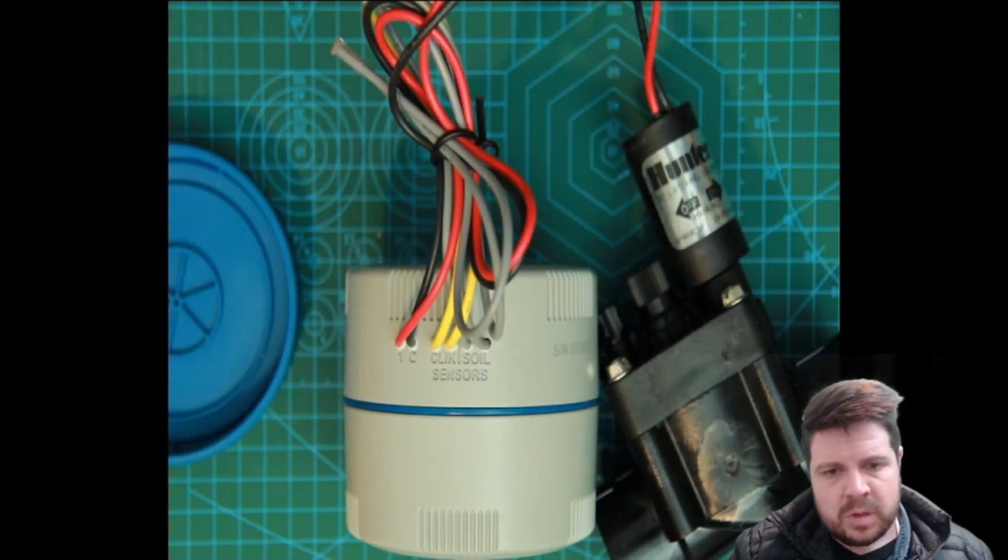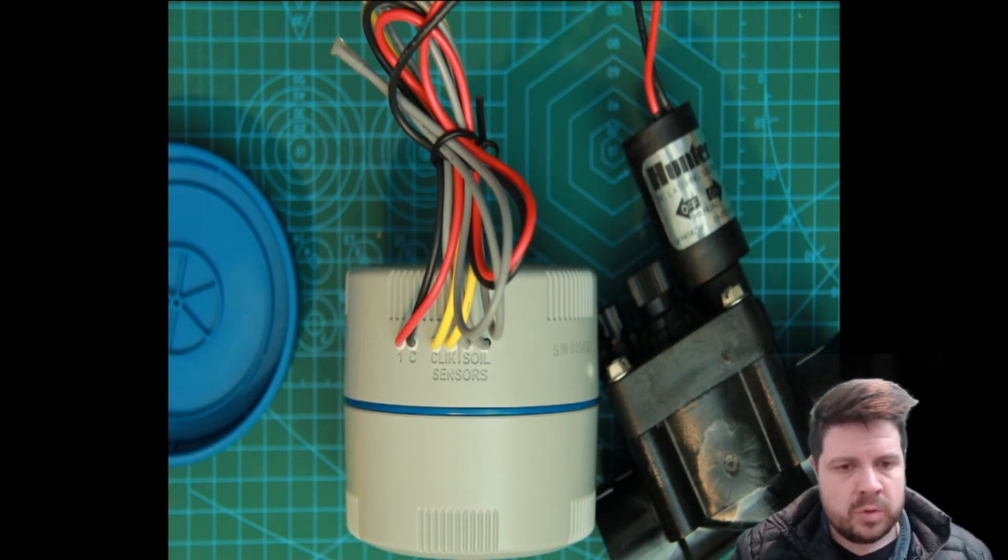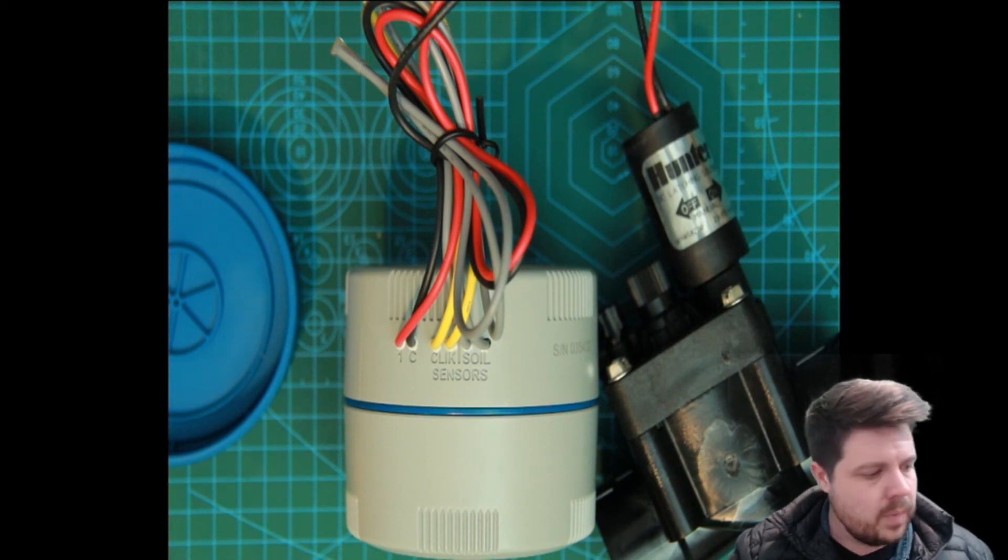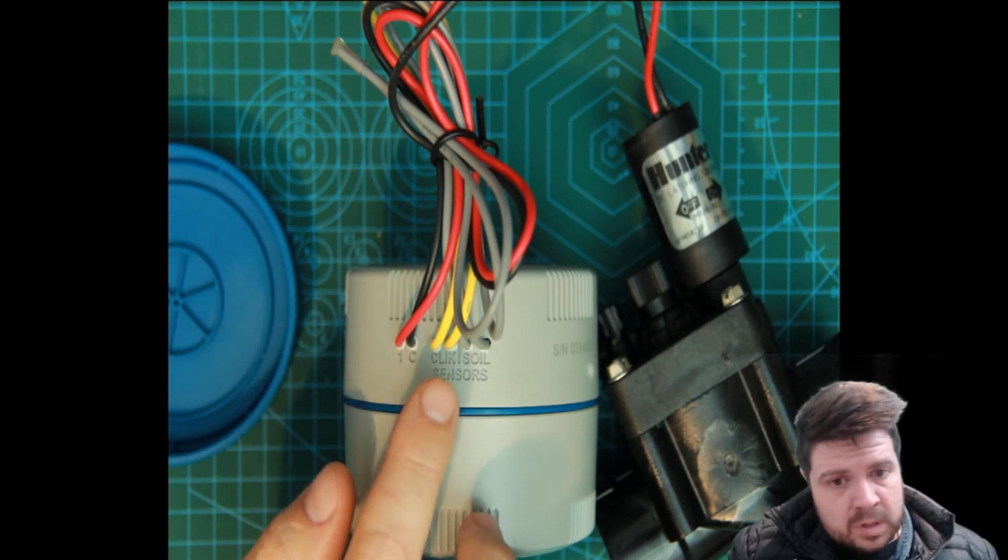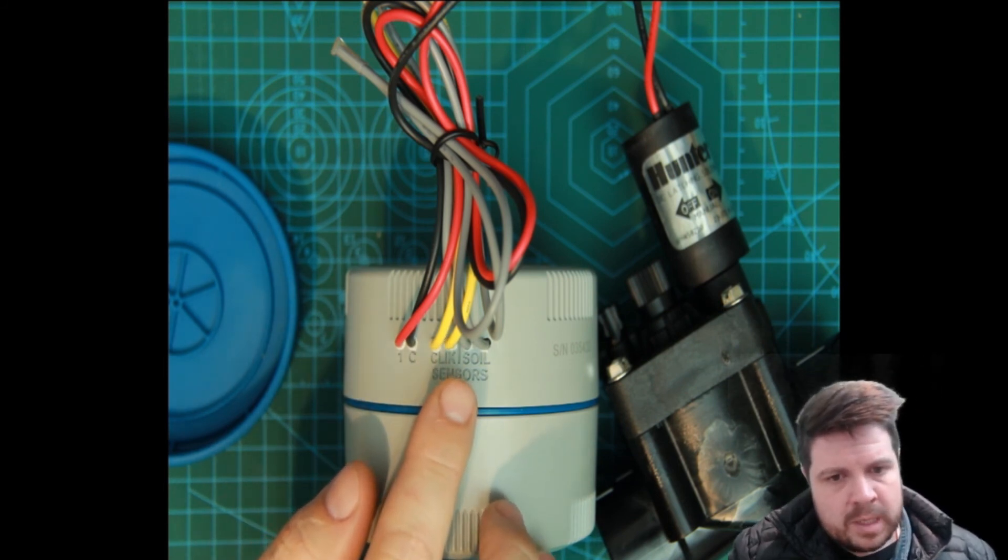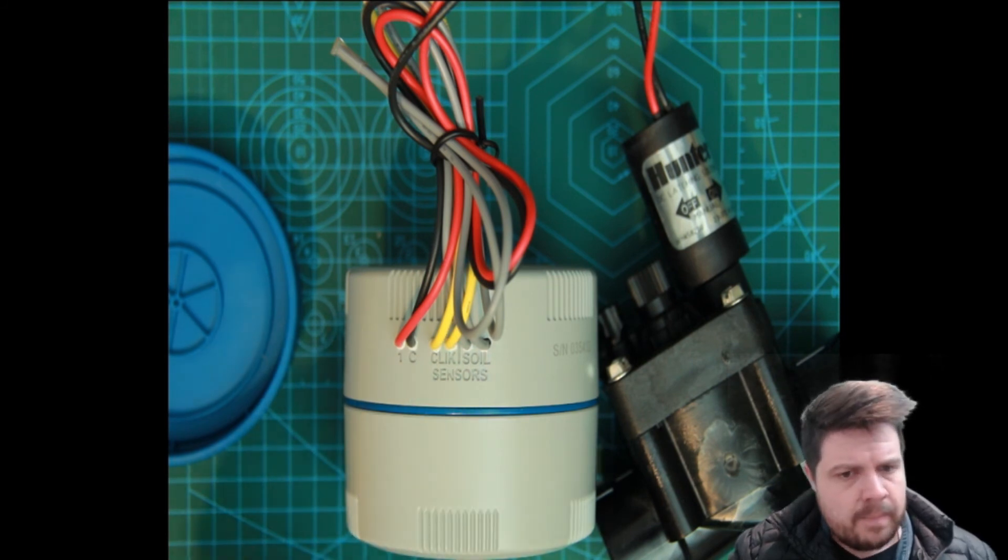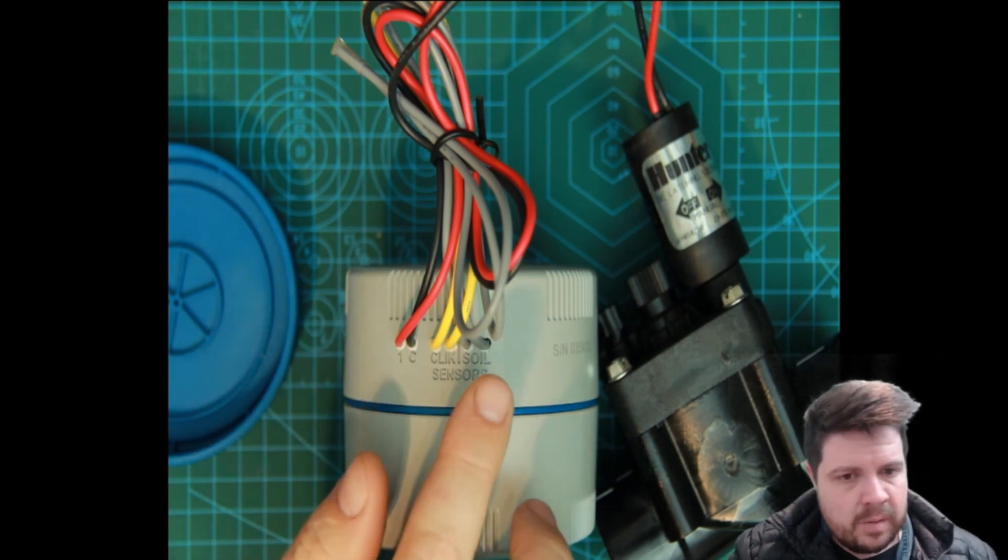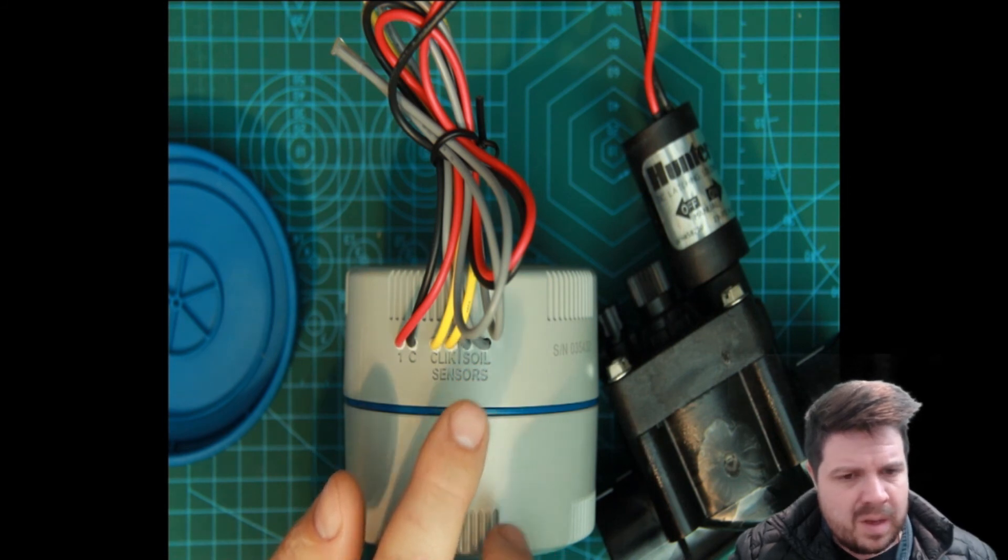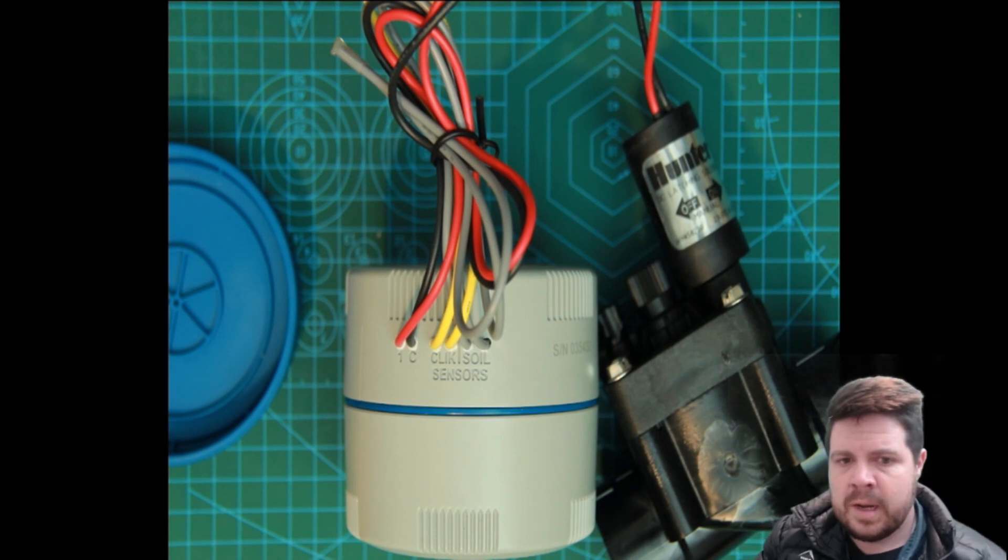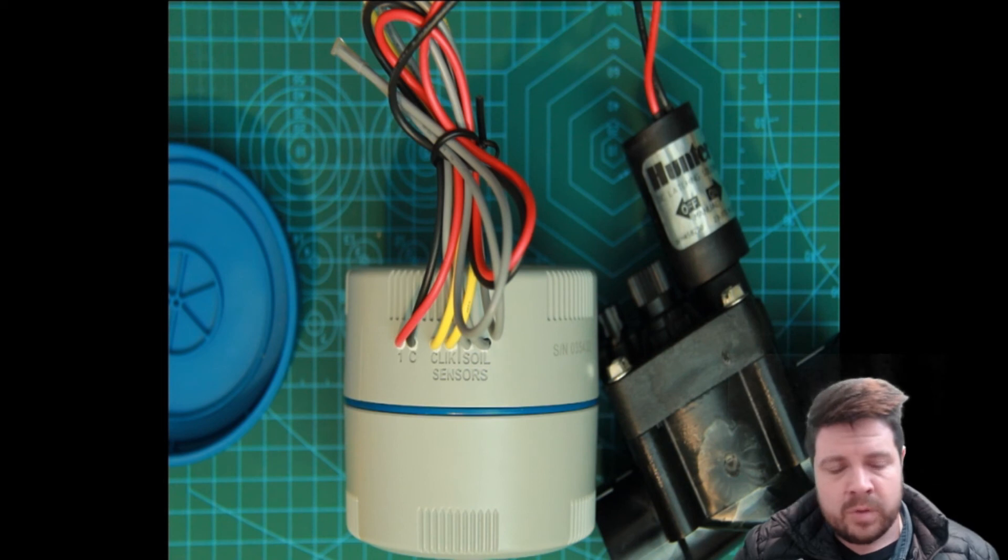Before we jump into the features of the app, I would like to point out one new addition on this Hunter Bluetooth node that was previously not seen in the old node. If you're familiar with the old nodes, you will have noticed there's always been this yellow wire that's been used to attach to a rain sensor. That's fantastic. But in addition to the rain sensor, they now have these grey wires over here, which can now be attached to a soil sensor. This is especially useful for situations like when you've got a green wall. Green walls are notoriously difficult to give the correct amount of water to. They're either too wet or they're too dry.